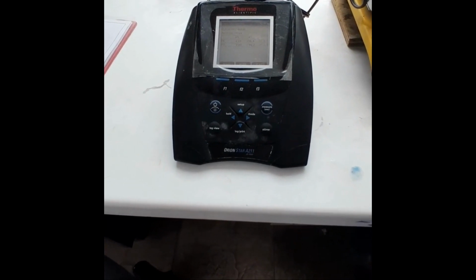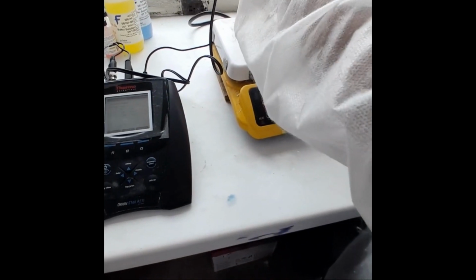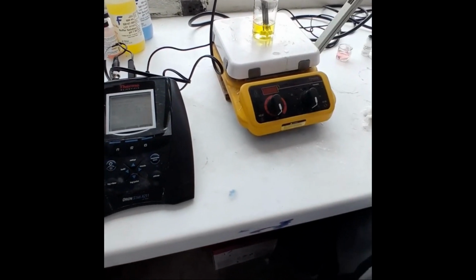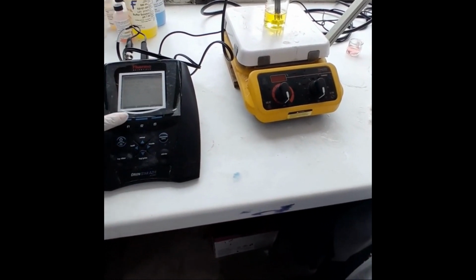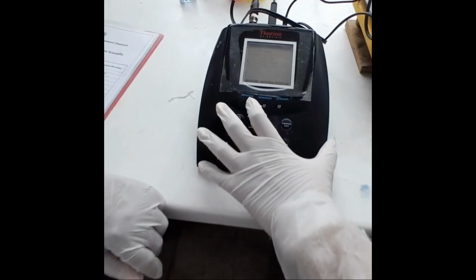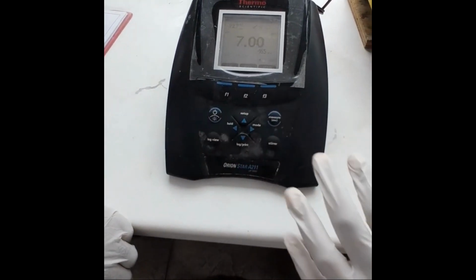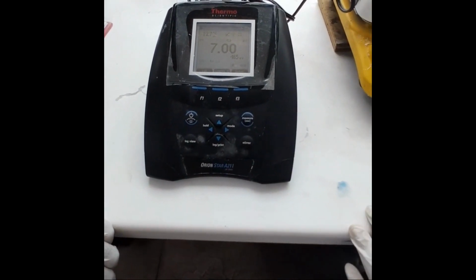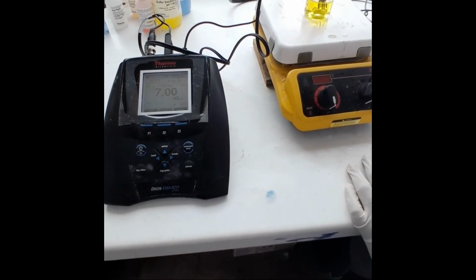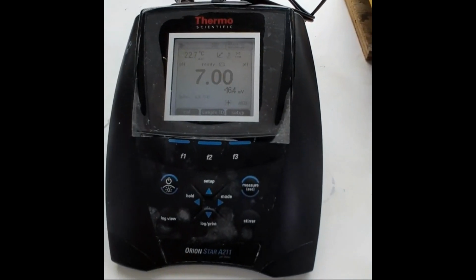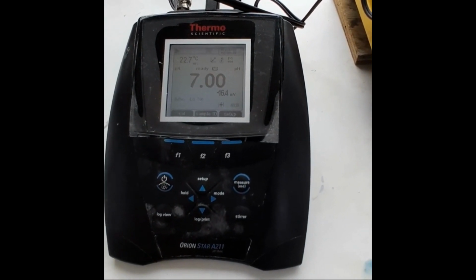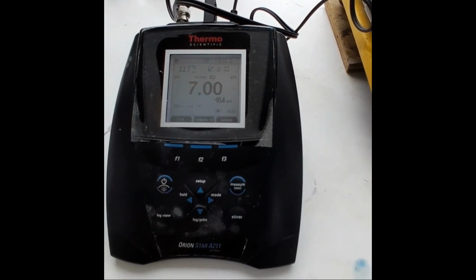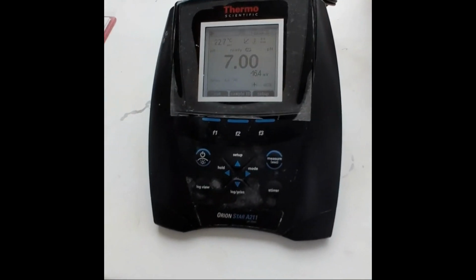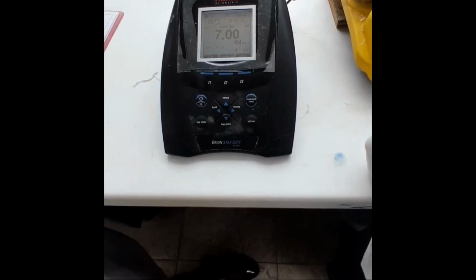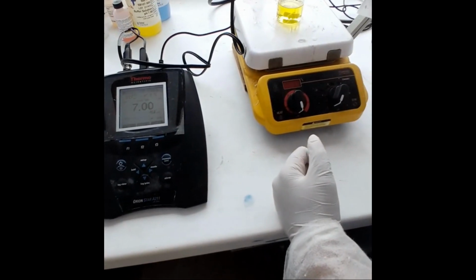So I'm going to wash the... No, you can see. I was going to wash the electrode and then measure. No, since it's in buffer 7 already, you can just press measure. I can measure. Okay. Whoa, pH buffer 7 is reading 7. So that was a very, very good calibration, Latoya. So we can move on to measuring our sample now. Having measured pH 7, we will measure our sample.